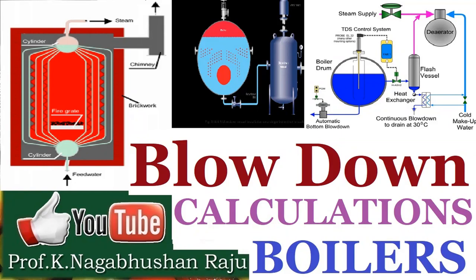In boiler performance evaluation, today we shall be discussing blowdown calculations and how to calculate blowdown losses while evaluating the performance of boilers. As we all know, when water is boiled and steam is generated, any dissolved solids contained in the water remain in the boiler. If more solids are put in with the feed water, they will concentrate and may eventually reach a level where their solubility in the water is exceeded and they deposit from the solution.